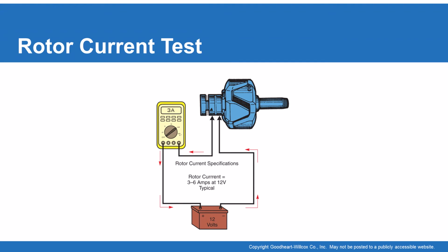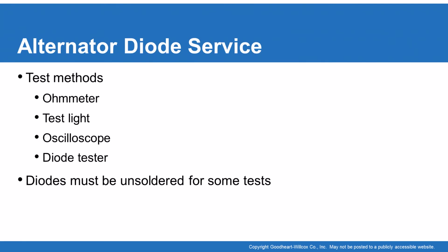Now, keep in mind there's another test, which is the rotor current test. And in this case, you could carefully run power to each of those slip ring contacts from a battery, positive and negative. And you don't necessarily have to run it through the meter. We could use an amp clamp. But what we're looking for is to see what the current being drawn through that field winding is. Typically a decent reading is around 3 amps in this case.